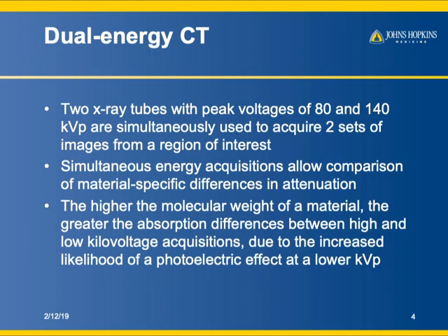A quick review: Dual Energy CT can be done with either two x-ray tubes or a single x-ray tube. The Siemens scanner uses two x-ray tubes; GE uses one. We're doing 80 and 140 kVP simultaneously, or in newer scanners 80 and 150. You acquire two sets of images from the region of interest — simultaneous energy acquisitions allowing comparison of material-specific differences in attenuation. The higher the molecular weight of a material, the greater the absorption differences between high and low kVP acquisitions, due to the increased likelihood of a photoelectric effect at lower kVP.